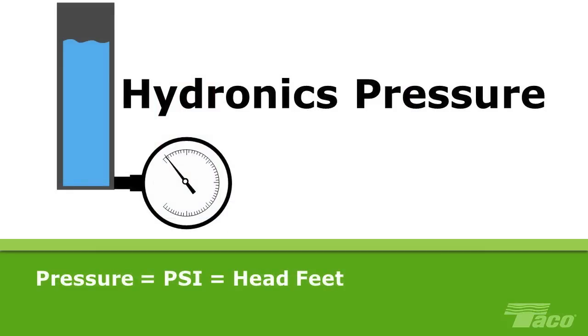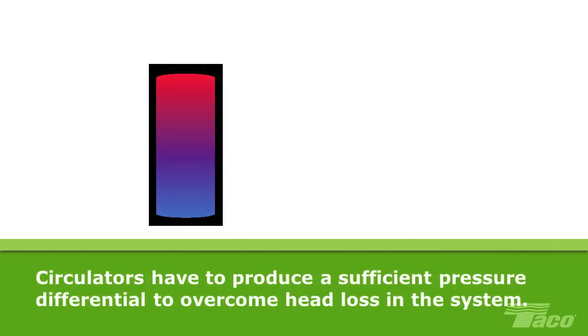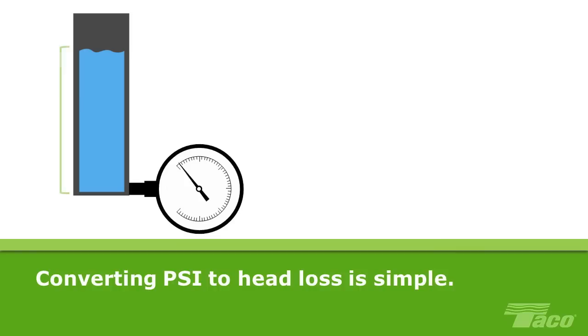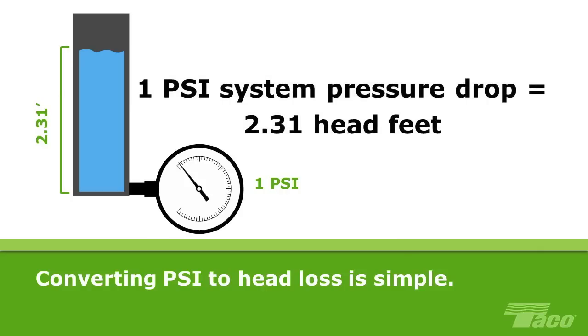Pressure is usually measured in psi, pounds per square inch. But in hydronics, we calculate pressure in terms of head pressure or head loss as measured in head feet. Technically, head is the total mechanical energy content of a fluid at a given point in a piping system. A circulator has to produce a sufficient pressure differential to overcome the pressure or head loss created in the piping by friction and by the various valves and fittings in the system. Converting psi to head loss is very simple: a column of water 2.31 feet or 28 inches high will have a gauge pressure at the bottom of 1 psi. Therefore, 1 psi of pressure drop in a system equals 2.31 feet of head.